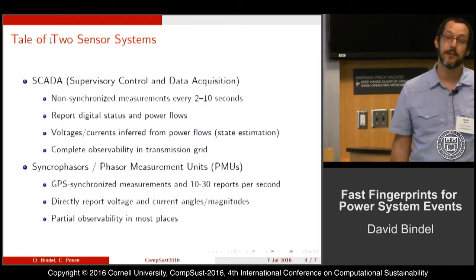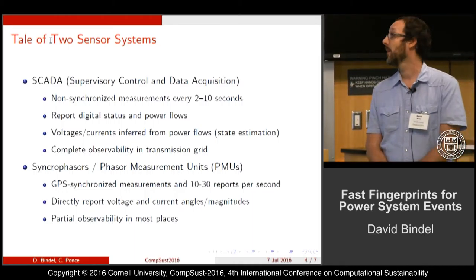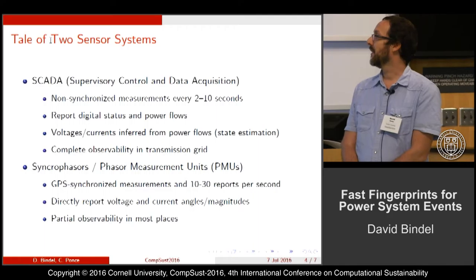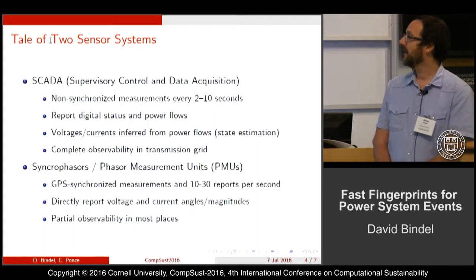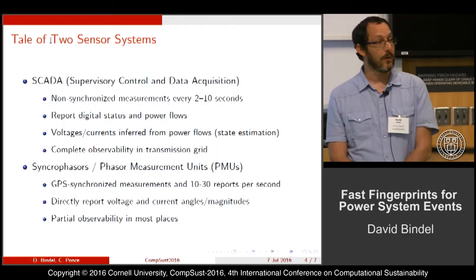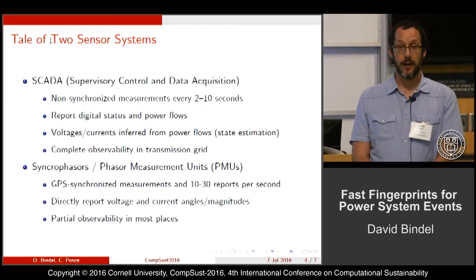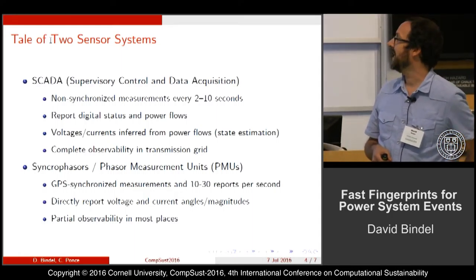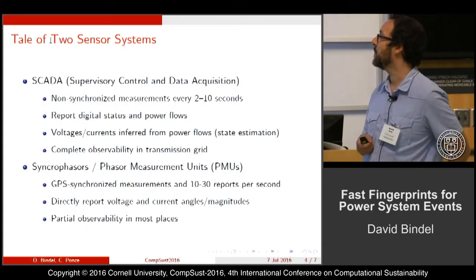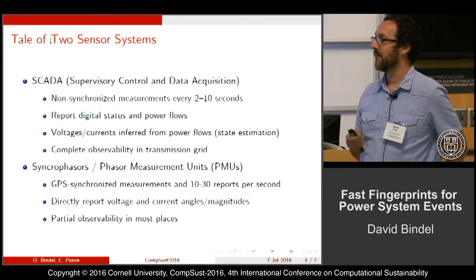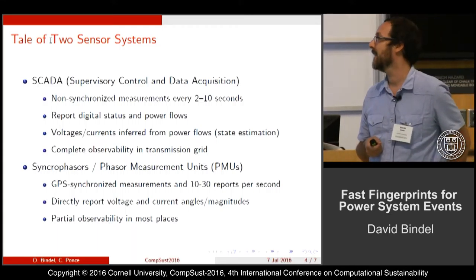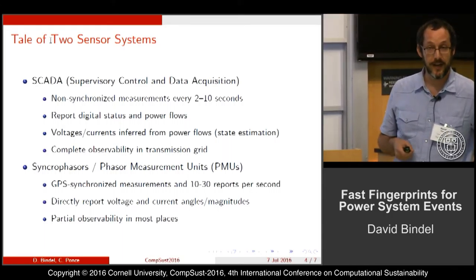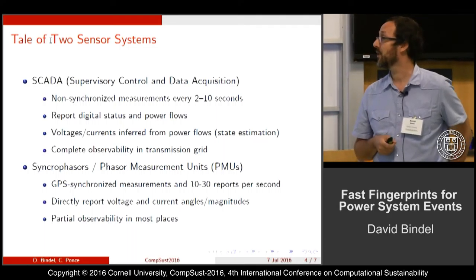There are really two sensor systems available for looking at the state of the power grid. The traditional one, which has been around for a long time, is the SCADA system. It reports on power flow and digital status measurements — for example, whether lines are tripped. You get a reading every two or ten seconds, so not super frequently. What we really get from this is power flows, whereas what we're interested in is voltage and current phasors. Going from one to the other requires a power flow computation — it's a nonlinear equation-solving problem.